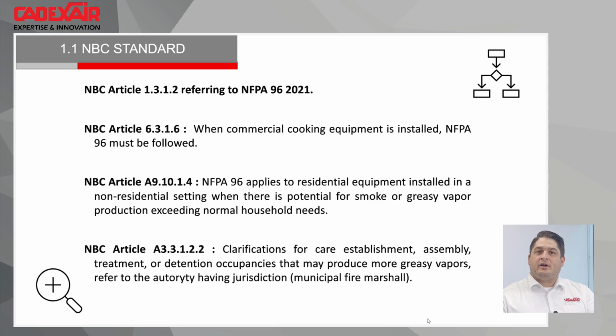And in fact, for article 3.3.1.2.2, we had some senior homes where they have maybe a residential appliance that could be used by multiple persons, but each one has their room, so some of them need to add an NFPA 96 exhaust system, others not. And at the end of the day, it's the municipal fire marshal that takes this decision. And I will say the municipal fire marshal is mainly the person that you need to contact if you have any question about whether you need commercial cooking appliances or not.